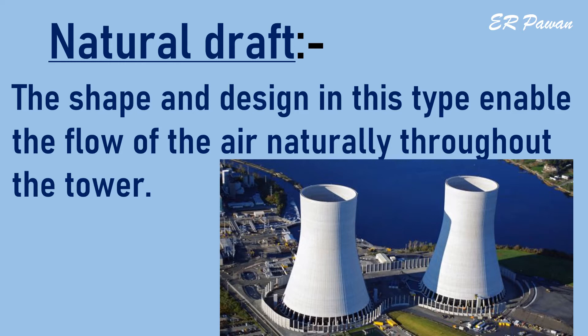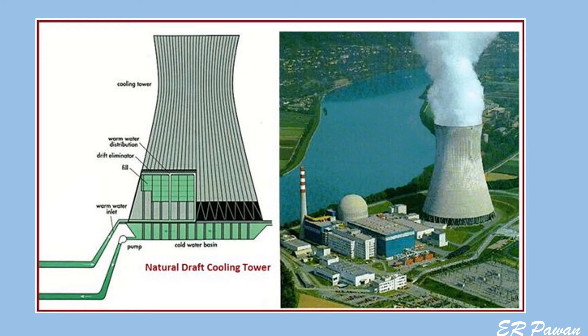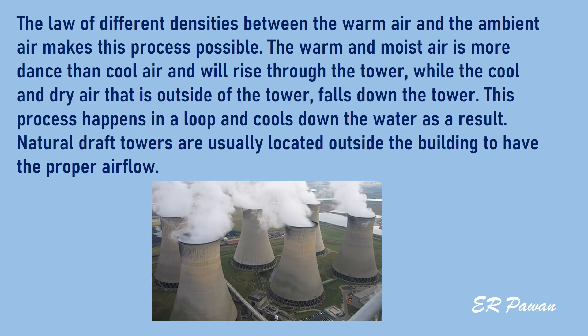Natural draft: the shape and design in this type enable the flow of air naturally throughout the tower. The law of different densities between the warm air and the ambient air makes this process possible. The warm and moist air is less dense than cool air and will rise through the tower, while the cool and dry air outside the tower falls down. This process happens in a loop and cools the water as a result. Natural draft towers are usually located outside the building.